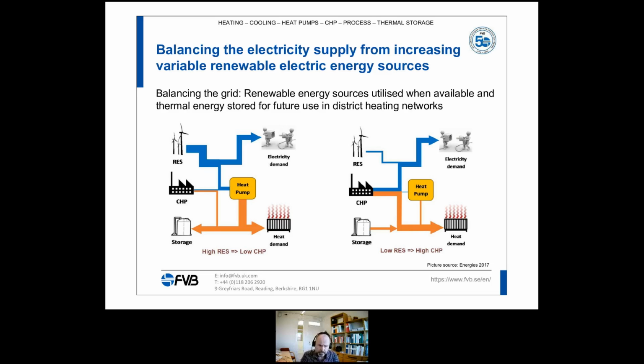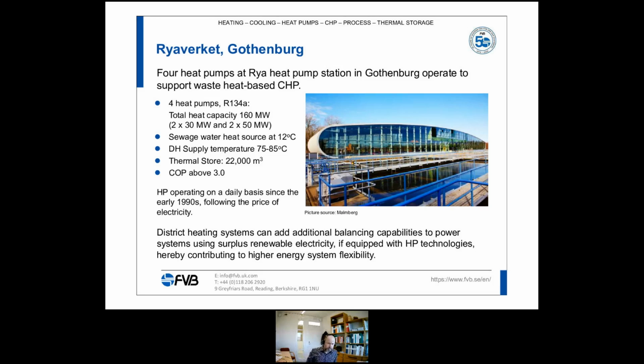So the combination of a CHP plant, heat pumps, and a thermal storage can really be used to balance the electricity grid. On the left-hand side, you see a scenario where you have a lot of renewable energy sources. You run the heat pump and you charge the storage. On the right-hand side, you have a scenario where there is almost none or very little renewables. Instead, you run the CHP plant and you discharge from the storage. And in real life, we have one example of this. It's Ryaverken in Gothenburg, where you have the integration of CHP, heat pumps, and thermal storage. And this plant has been running since the early 90s, purely on a start and stop basis, daily.